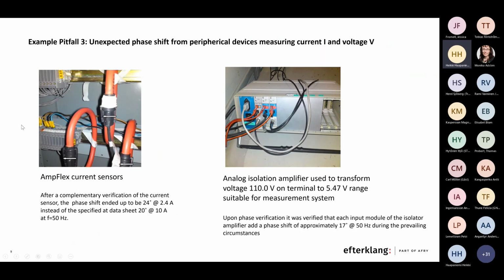We then used standard AmpFlex current sensors, and they are delivered with data sheets, which are specified like you should have a phase shift of about 20 degrees at 10 amperes. But in this case, we were just measuring 2.4 amperes. So you cannot rely on the data sheet. You must do a verification of the phase for a certain instrument, at a certain amplitude level. So when we verified this, it ended up that the added phase shift for these sensors was 24 degrees.